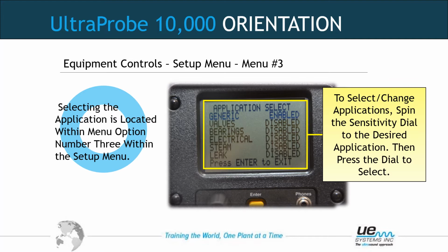You will then receive warning information that you will delete all the records on the onboard memory. That's fine, proceed. Then leak is enabled and you have a clean memory on the Ultraprobe 10,000. The SD card, however, has not been deleted. No information was removed from the SD card at this point.